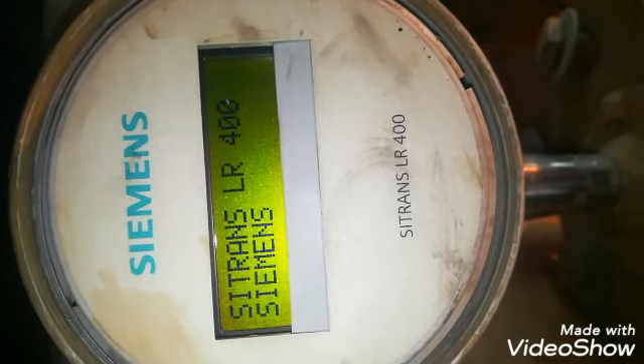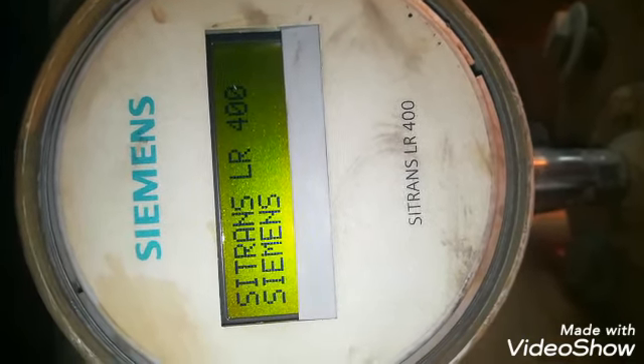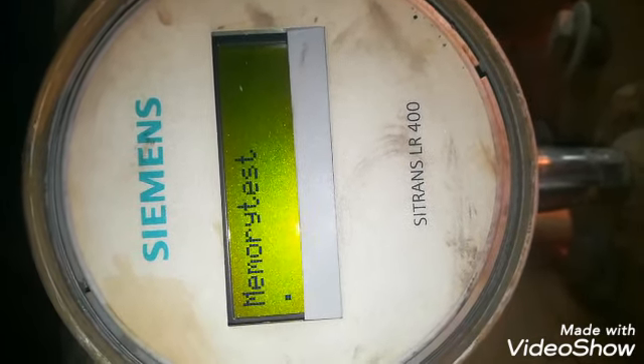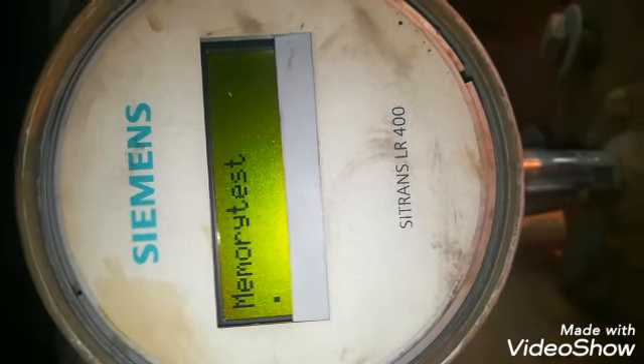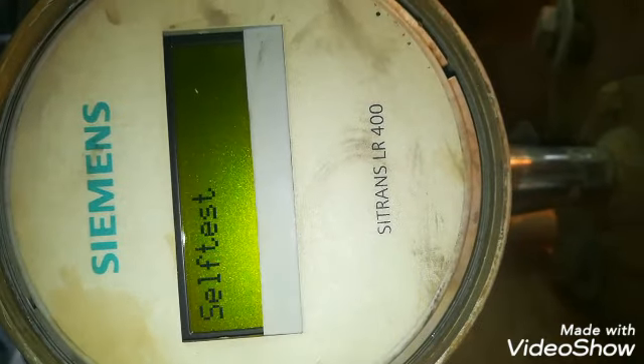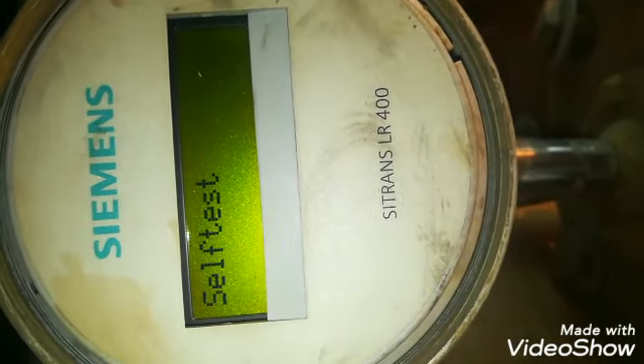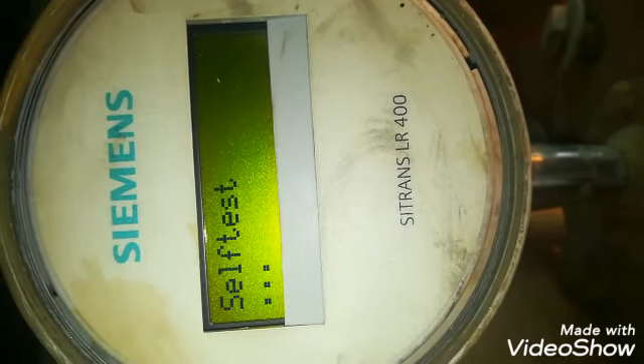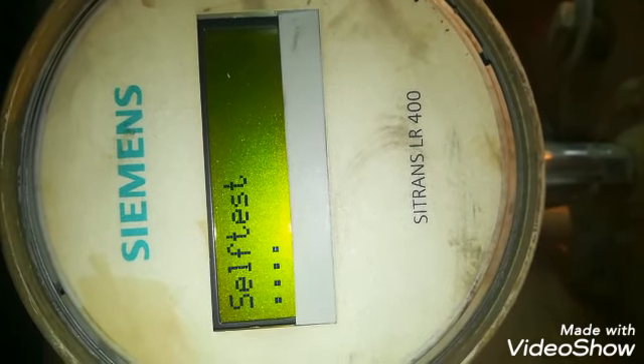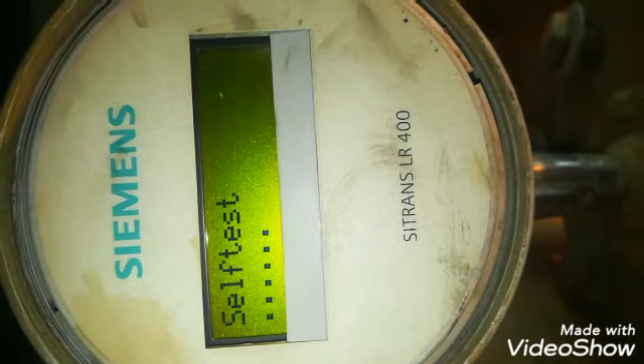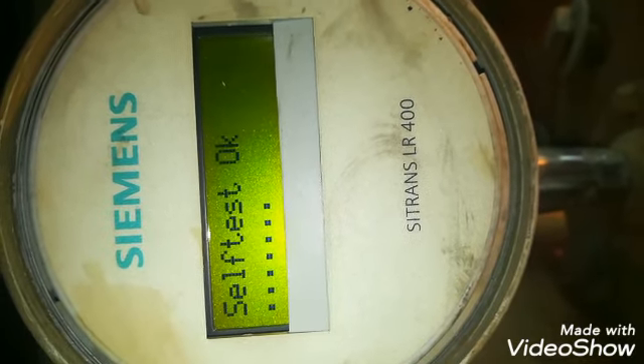So at the start it will display like this. It will show its model number, then it will test its memory, that its memory is OK. All the parameters are safe. It will run the memory test, then it will run the self test. In self test it will check the horn and the connection, all the electronics are OK, parameters are OK, memory is OK. So if all is OK, then it will show the normal display.